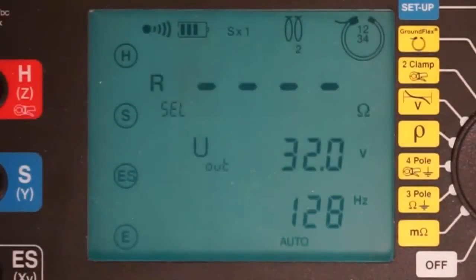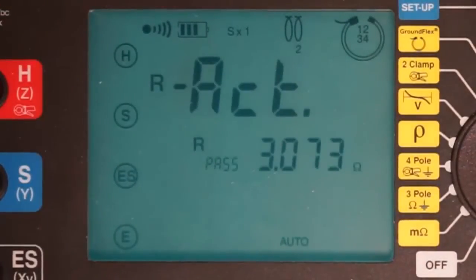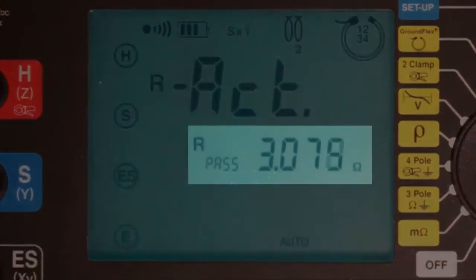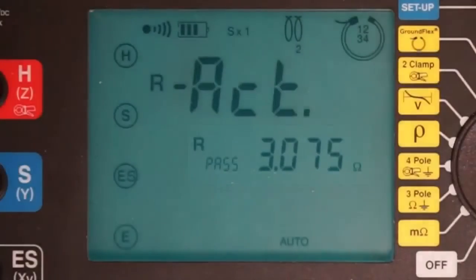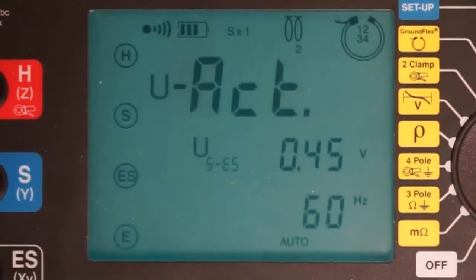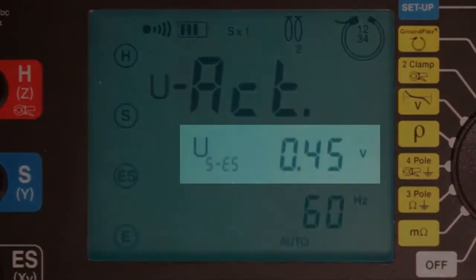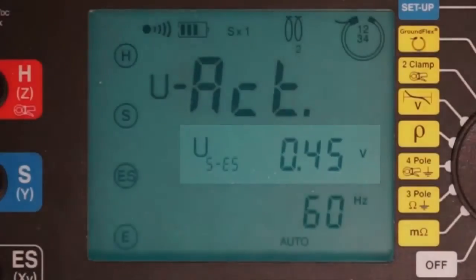A second press of the display button provides us with our first measurement, the actual passive resistance of the 4 tower legs in combination. As you can see, this is slightly over 3 ohms. Another press of the display button shows the voltage between the black output terminal, attached to the instrument via the ES connector, and the electrode connected to the instrument via the blue S connector. This value is labeled U sub SES, and in our demonstration is around 0.45 volts.